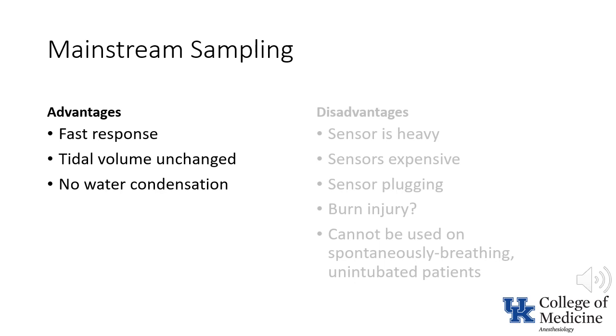The absence of water condensation is also an advantage of mainstream capnometry. Because the device is heated, no water condensation occurs. This is in contrast to a sidestream capnometer where a water trap is necessary due to condensation, and the presence of water in the water trap can result in inaccurate readings.